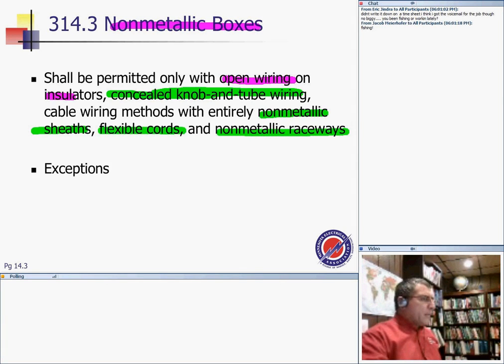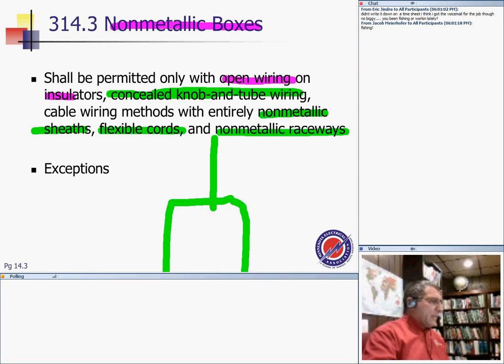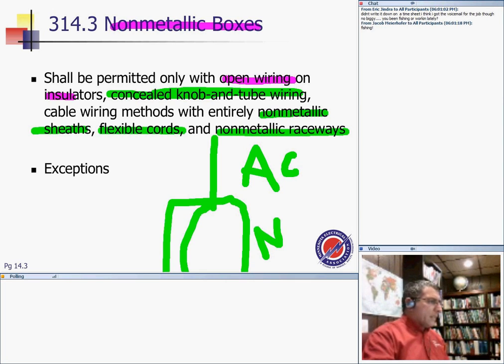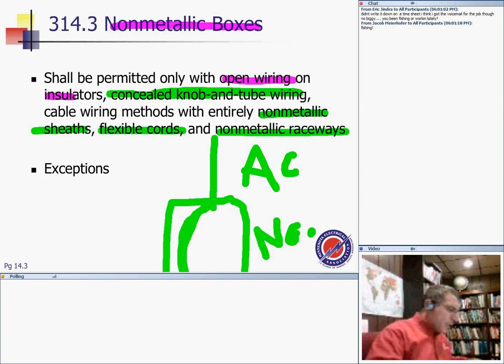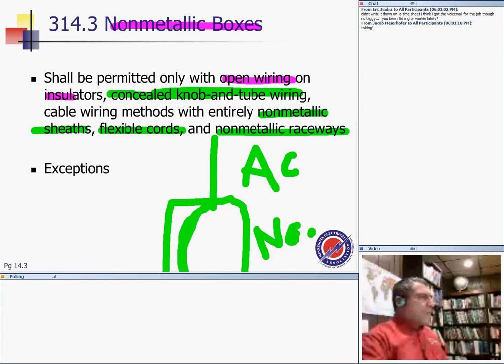The point, if you are using it, is they want to make sure that the cables are bonded together. You have some type of a means where you can bring an MC cable here, another MC cable here, and you bond the shield of the MC cable to the other shield of the MC cable, or an AC cable. If you have an AC cable and an AC cable here, and this is a non-metallic box, they're not bonded, so you have to bond the two together. So for the most part, it's limited to non-metallic wiring methods.